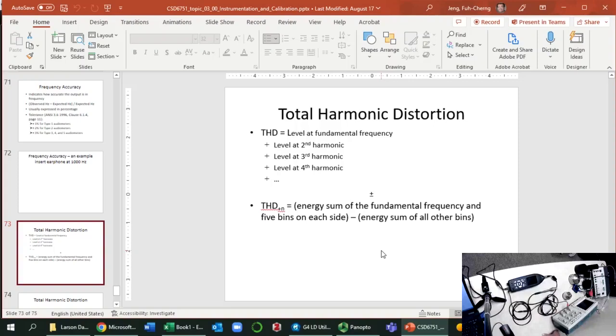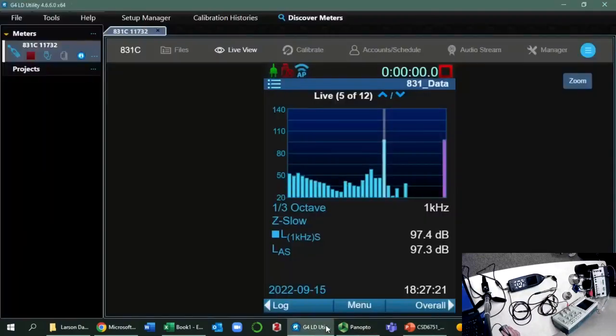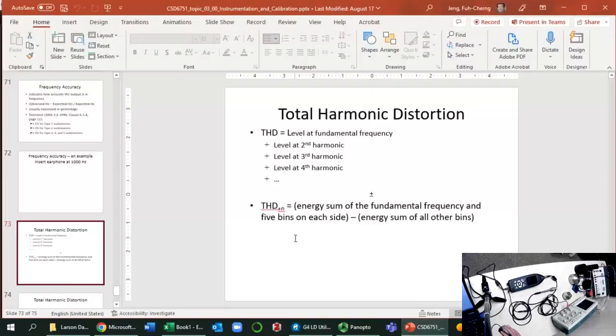I cannot show you directly. The closest I can show you is here: if the fundamental is 100, then you have 200, 300, 400, 500, and so on. You have to do this manually, adding them all together, but this device doesn't deal with that. The concept still stands true, and I still want you to understand it, because total harmonic distortion is also important when calibrating the audiometer, even though it's not that critical, it's still one important parameter.